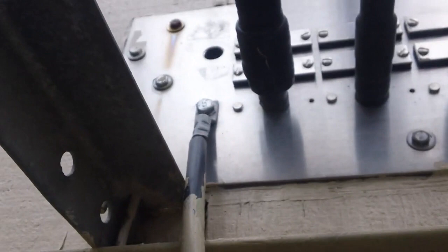Here's an example of an entry plate into the building, and this wire here and this one are both earth ground, buried within the building when it was constructed. All the equipment in this room is grounded directly to earth ground — everything is hooked up to it.